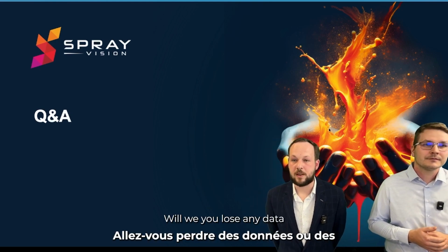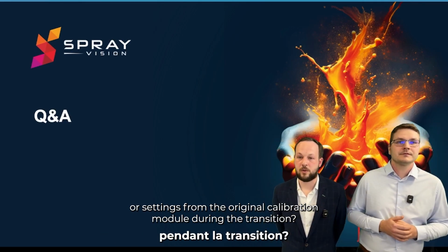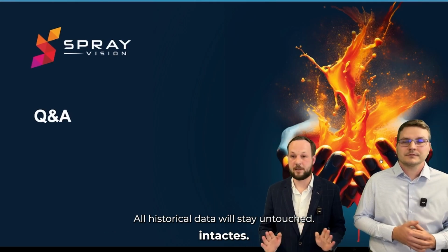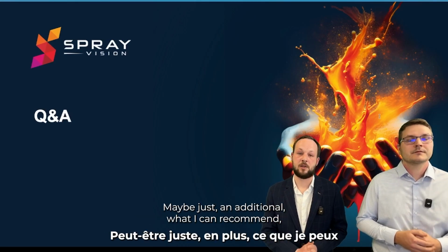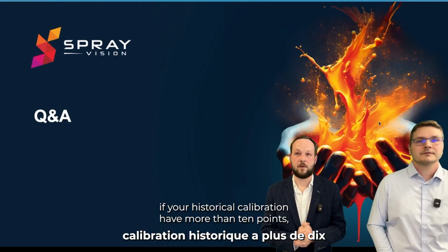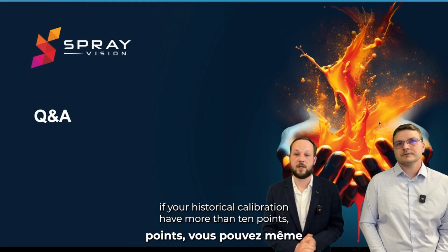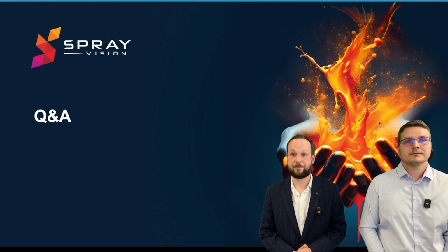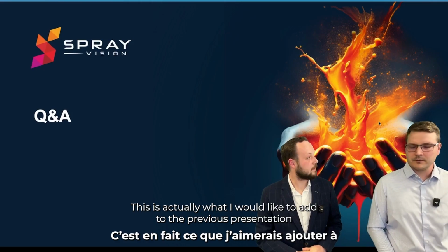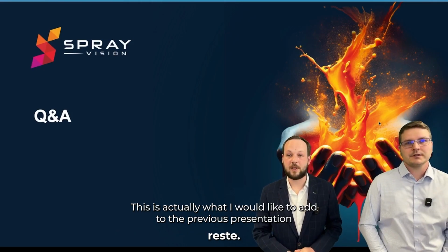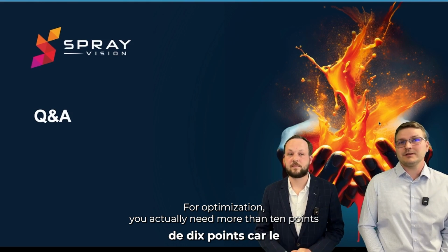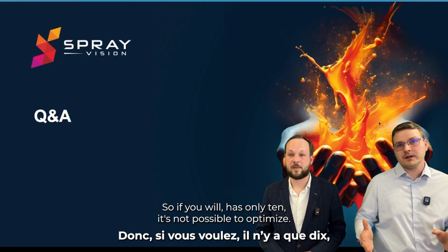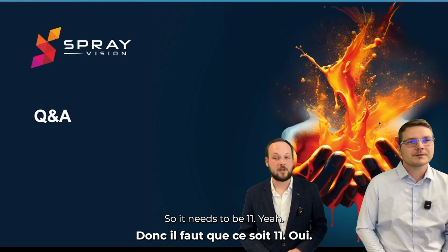Will we lose any data or settings from the original calibration module during the transition? Simply no. All historical data will stay untouched. Maybe just in addition, what I can recommend: if your historical calibration has more than 10 points, you can even use the new calibration module to optimize it. This is actually what I would like to add to the previous presentation. For optimization, you actually need more than 10 points, because the minimum for the calibration now is 10. So if you only have 10, it's not possible to optimize. It needs to be 11.